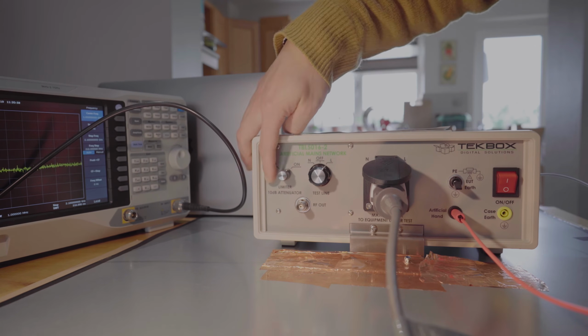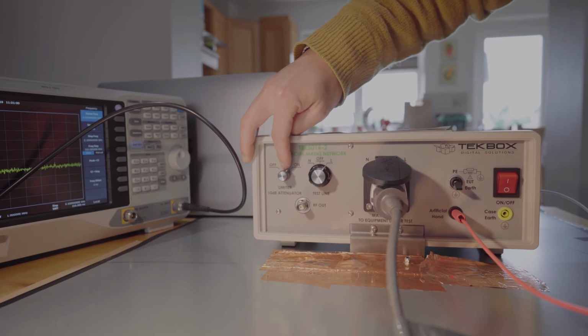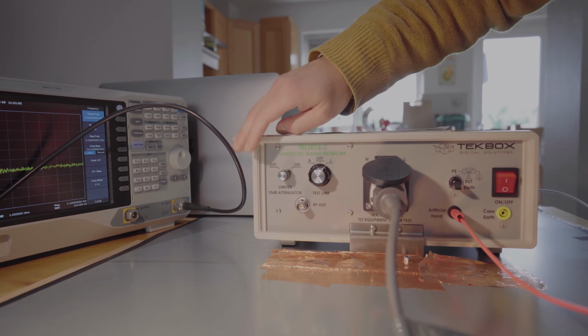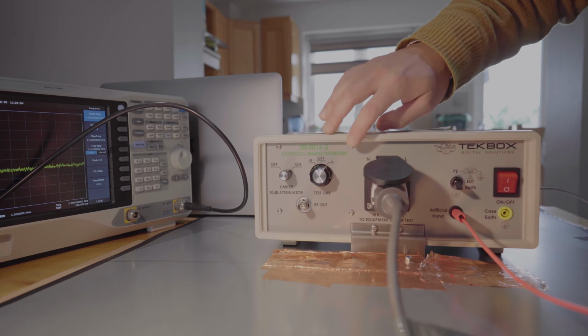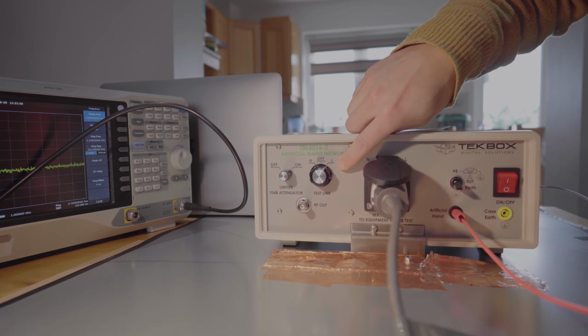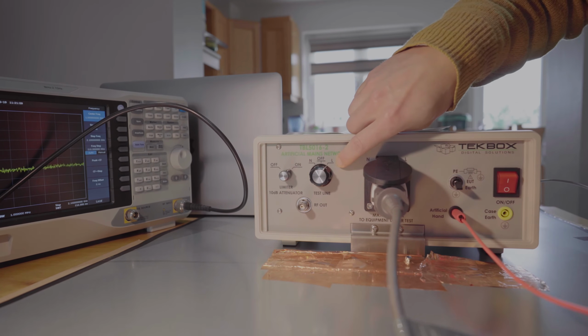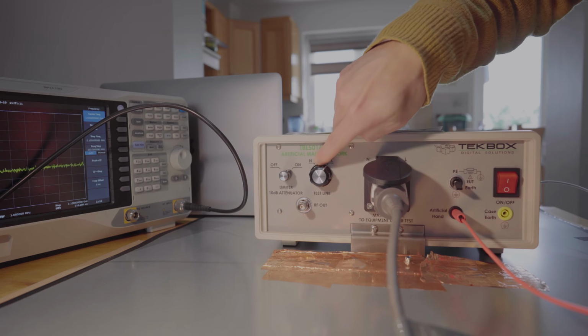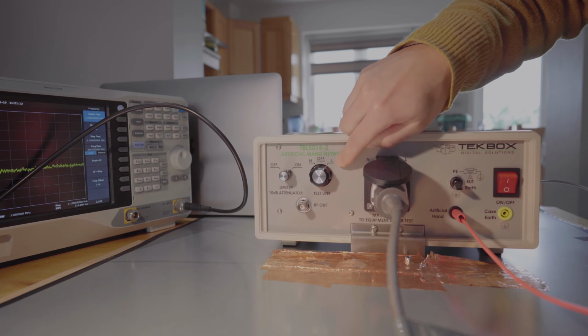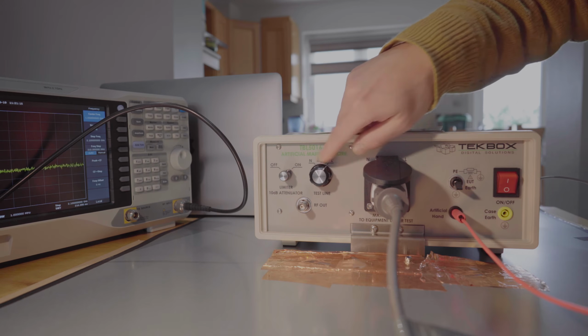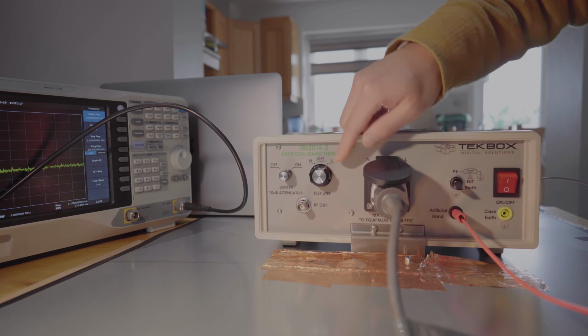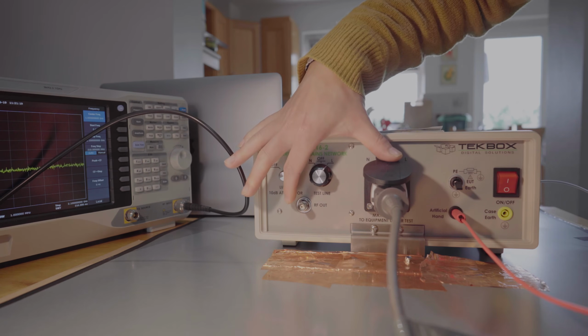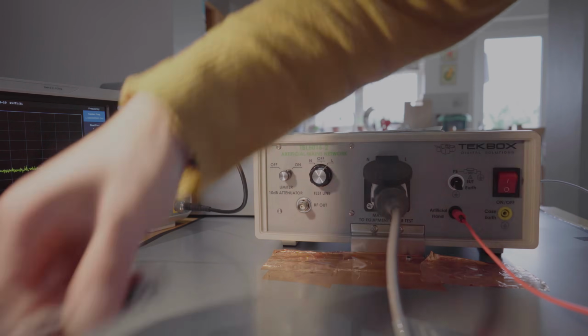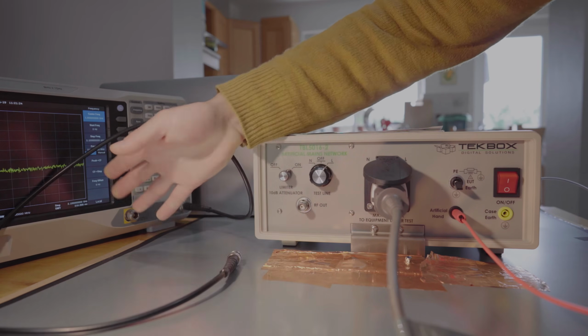You have the 10 dB attenuator or a transient limiter. You can choose on or off. And here you can select to either measure the line voltage or the neutral voltage. Basically, the conducted noise can be measured from either line. This is the RF output of the LISN, which you connect to your spectrum analyzer.